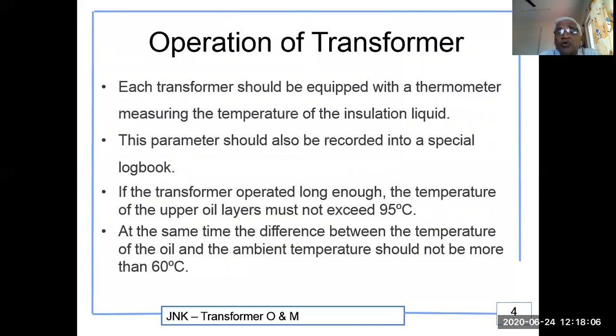Each transformer should be equipped with a thermometer measuring the temperature of the insulation liquid. This parameter should also be recorded into the special logbook. If the transformer is operated long enough, the temperature of the upper oil layer must not exceed 95 degrees. At the same time, the difference between the temperature of the oil and the ambient temperature should not be more than 60 degrees.